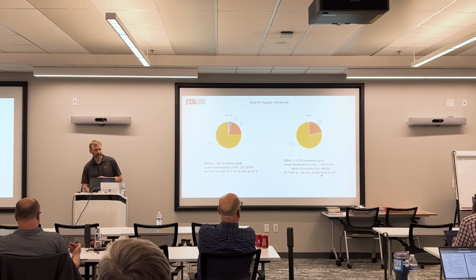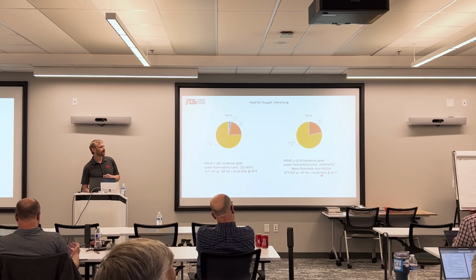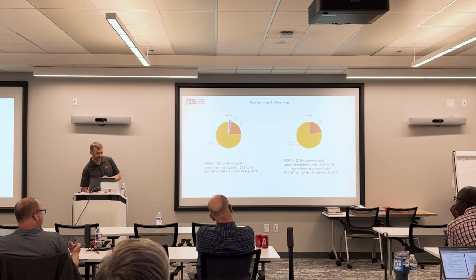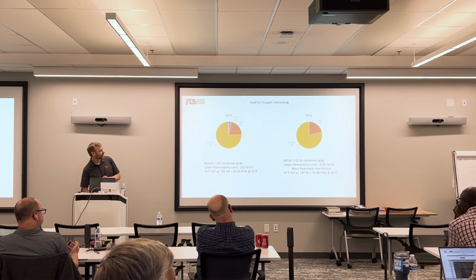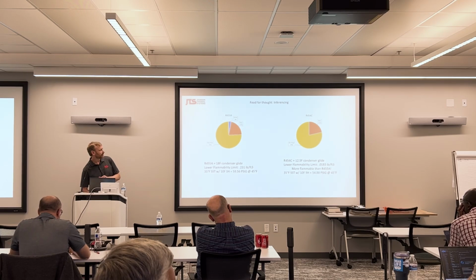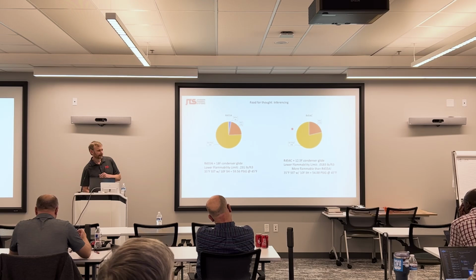So I think there was a question. Oh, yeah. I would think that R32 having a higher partial pressure, you'd leak it, therefore your flammability would go down. Yeah, so repeated... I think you're leaking the CO2 component. Oh, the R32 is the CO2? No, the 744 is your CO2 component. Okay. So as this component leaks off and gets smaller, you're going to look more like R454C. Okay. So which one is the more flammable component?